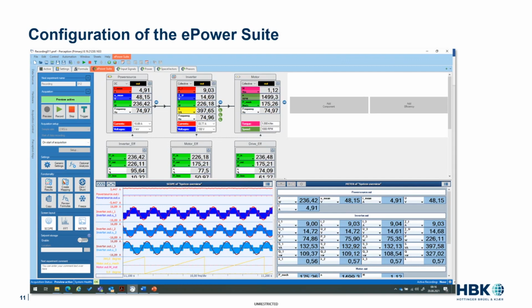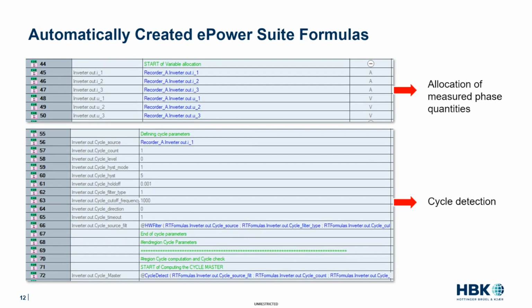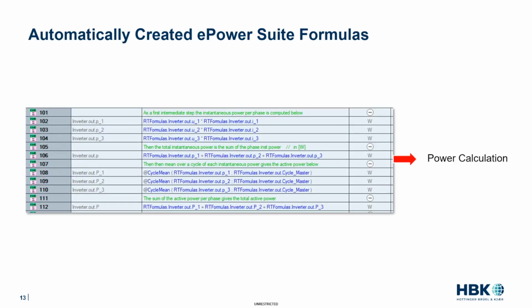Independent of your customized measurement setup, you can see this here. First, there's an allocation of the measured quantities, then the important cycle detection. I'm showing you this not to look at every line in detail, but to show that the step-by-step procedure I explained is realized in the background—including the power calculation: multiplying voltage and current per phase, summing over all phases, then averaging per phase to get per-phase active power and overall active power, all done automatically.